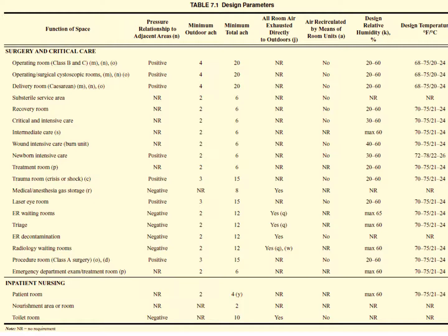So it's not like it's 20% higher or 30% higher, it's 5 times, 500% higher. That's primarily because the hotel would not design HVAC systems using a mandatory minimum air change per hour table like this. The hotel would design systems to keep people comfortable, control odors, and maintain acceptable indoor air quality. There's nothing dangerous about the air in the hotel. But we use this table of air change rates, and we exclusively use this. We do not allow any alternative approaches.